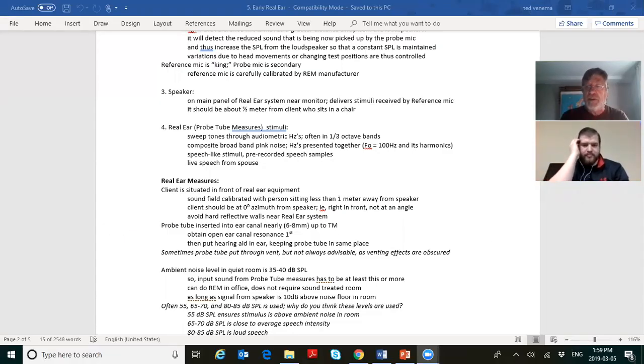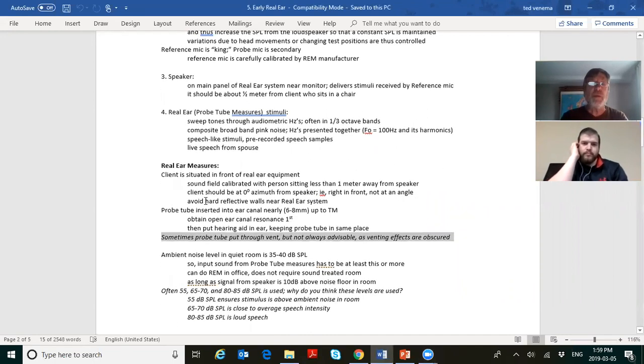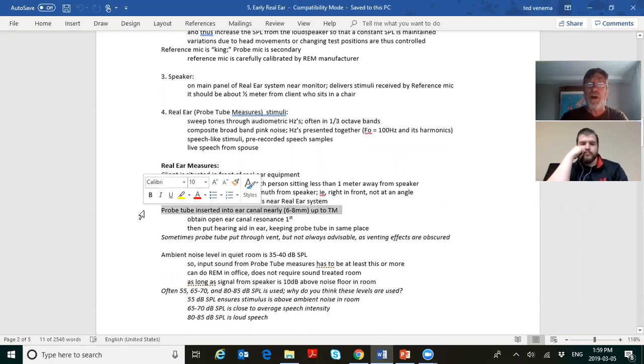All right. The trickiest part in real ear measurement is putting the tube in place. That's the hardest part. And a visual way is to look in with an otoscope and see that it's done right. And the other way is to make sure that the black ring is at the tragus, and if you've done that, you're okay.